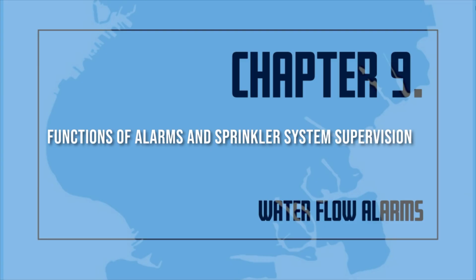Water flow alarms and fire alarms give warning of the actual occurrence of a fire. They also signal when water flows through the system due to broken pipes. Alarms alert occupants and summon the fire department. Any signal, whether water flow or supervisory, may be used to sound an audible local sprinkler alarm.